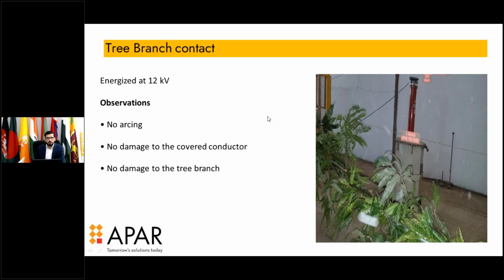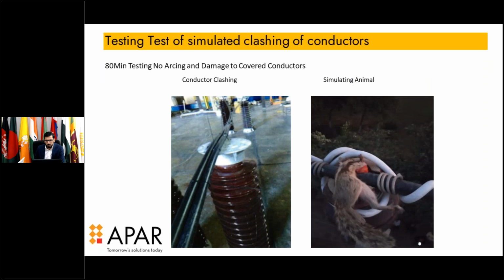We also do testing in simulated conditions, like keeping both conductors together and testing for 80 minutes: no arcing, no damage to the conductors while keeping them together. Then simulating with animals also, whether they are able to bite it or not. There are no bites, nothing. XLPE is a hard material; they are not able to cut the surface.